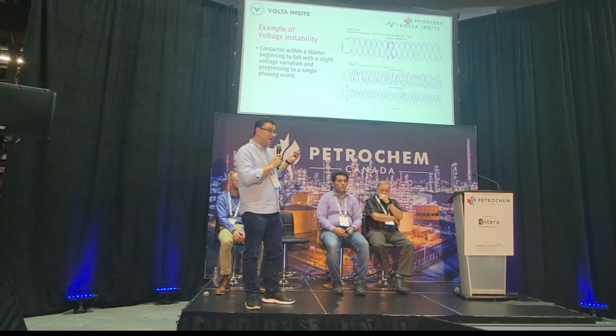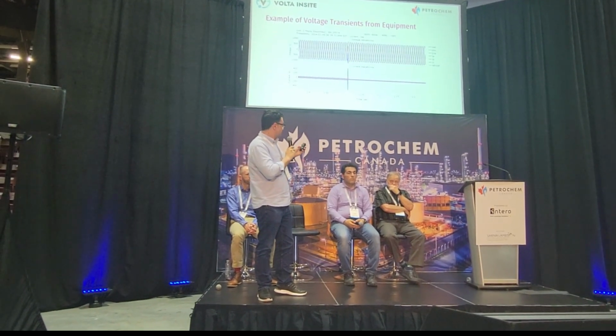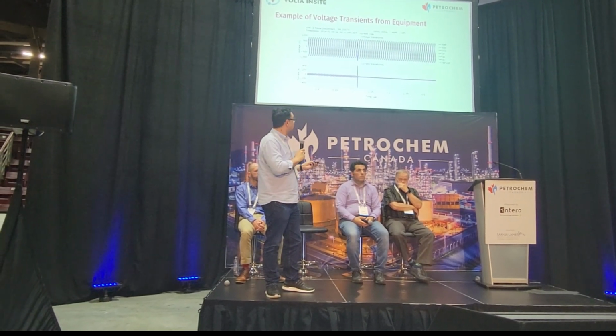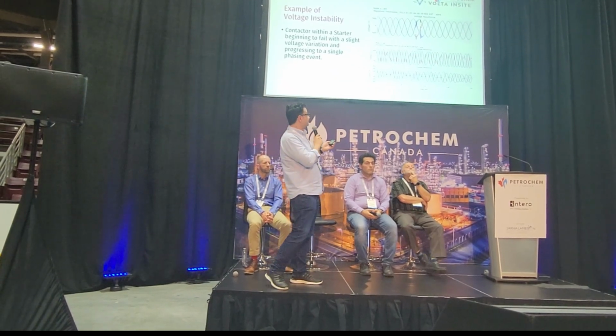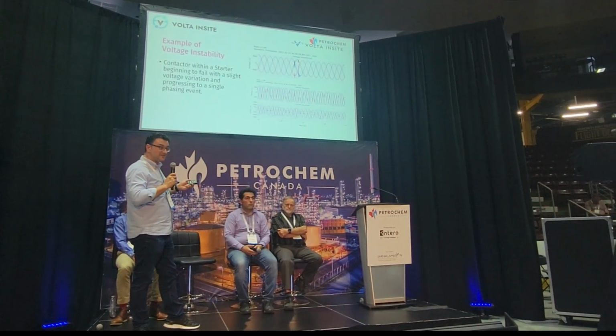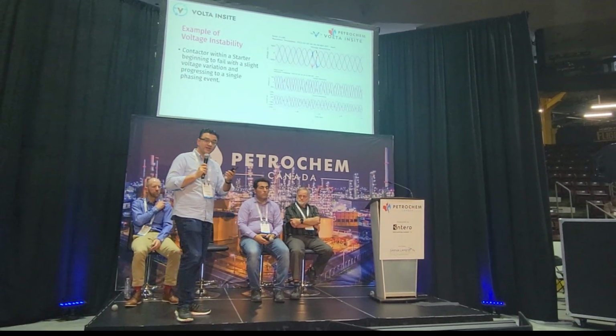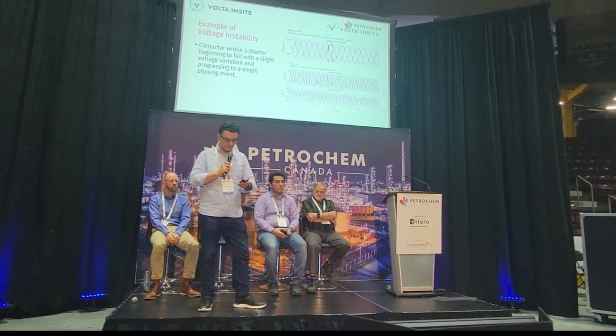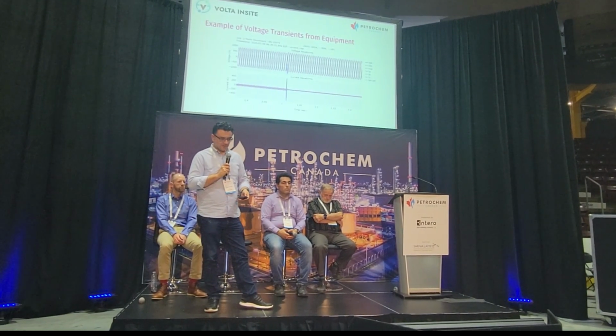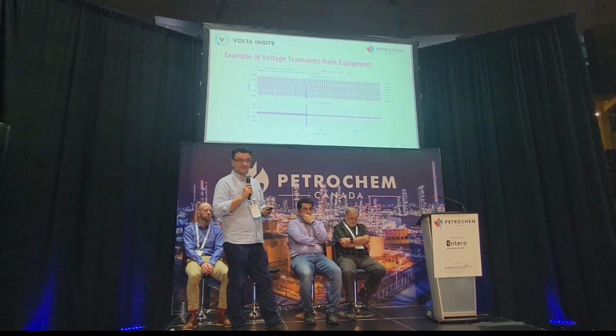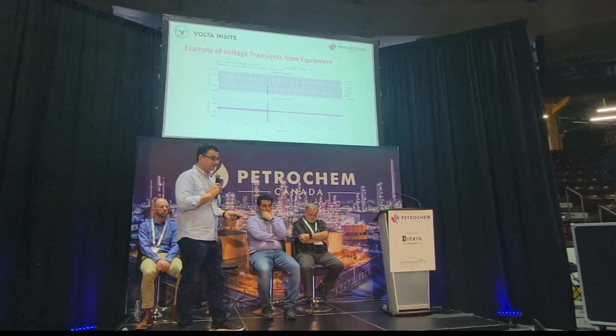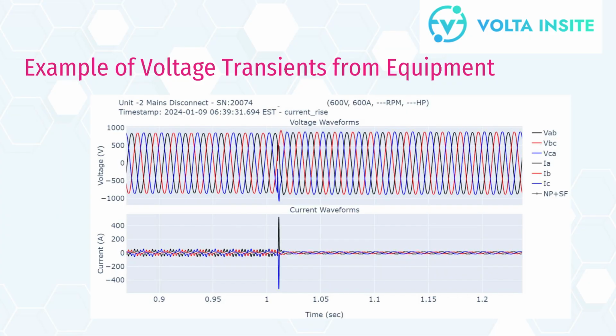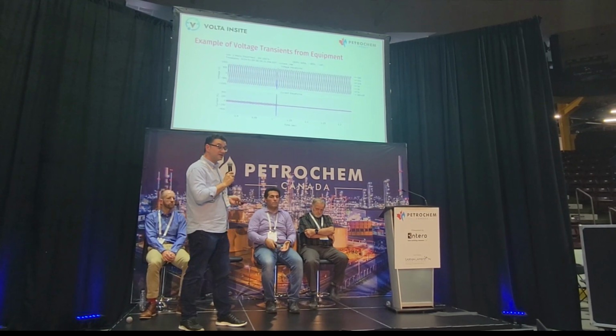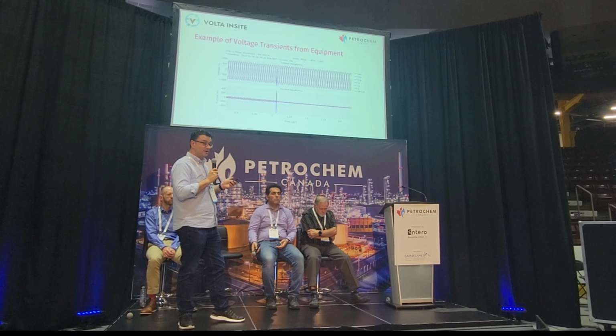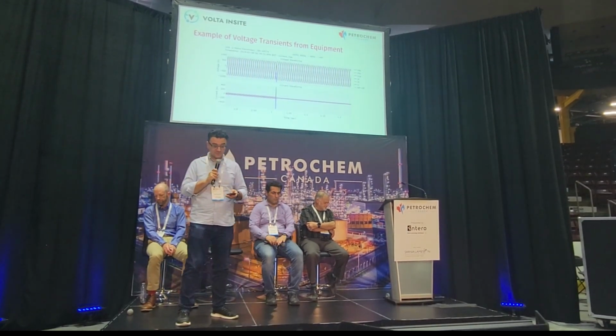So by continuously monitoring these systems, you can actually trend over time the anomalies and how bad they get, and be able to create a predictive action to fix the problem before it becomes catastrophic. Here's another example of a voltage transient, and this is specific to a facility at the utility end. So there's a voltage variation that happens, and that voltage variation creates a big current spike within the facility, and that may throw off the equipment within it, also creating downtime, even though it may be temporary.